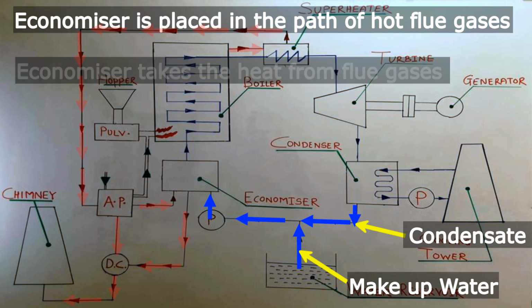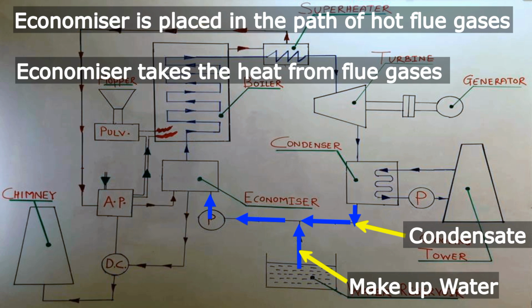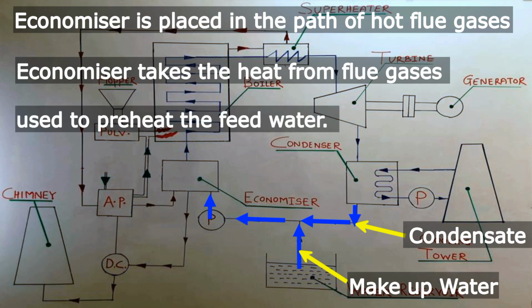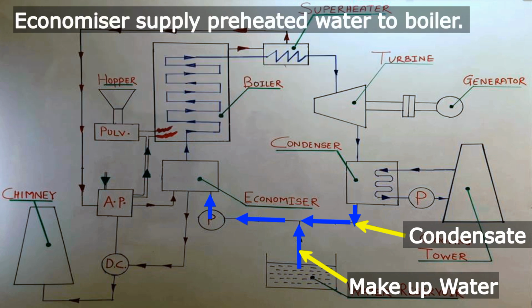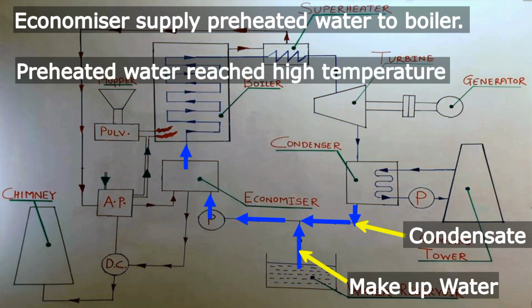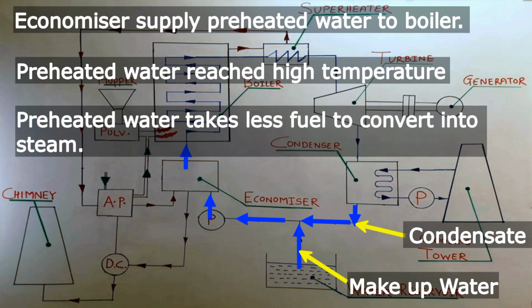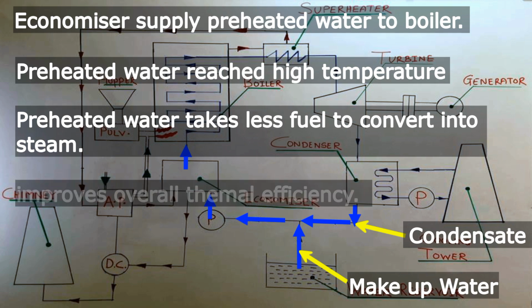Hence, economizer takes heat from the flue gases in order to preheat the feeding water, that is condensate plus makeup water mixture. So therefore, when economizer supplies this feed water to the boiler, it is already heated up to a certain temperature, and hence in the boiler it requires less heat to convert it into the steam, and therefore it requires less fuel and hence improves the overall efficiency of the thermal power plant.